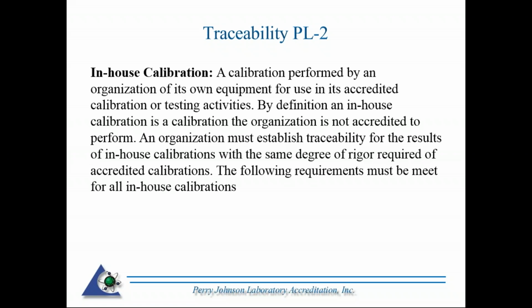One thing we do need to be aware of when we do assessments is whether any of these in-house calibrations are taking place. Like I said, they're assessed just like an accredited calibration, and somebody technically competent in that area would need to be made available for that assessment.